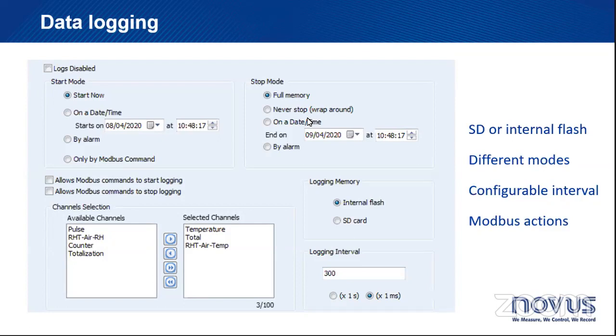On the stop mode, there is a very important point: you have two main types of stop logging. You have four actually, but two are most important. One is when memory is full. If you're using internal memory, when you reach 512,000 logs, the FieldLogger stops logging. The other is never stop, which is a wraparound mode. When you reach the end of the memory, FieldLogger starts overwriting the older data.